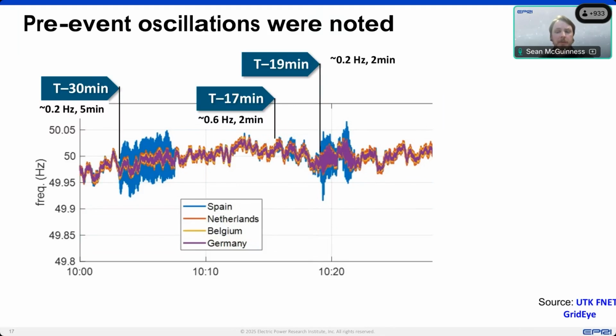Some of the key events we discovered probably began about 30 minutes before the blackout, and you can see this on the left-hand side. These are frequency traces taken from the FNet, or frequency net, with PMUs dotted all around the European grid. You can see there are measurements in Spain, Netherlands, Belgium, and Germany. At that T-minus 30 minute mark, there was quite a notable oscillation in frequency in Spain. This oscillation was about 0.2 hertz and it persisted for approximately 5 minutes before it was damped out. It was quite sustained for that 5-minute period until either it was damped out itself or the operators took some action to mitigate it. So that went away and the grid went back to normal.